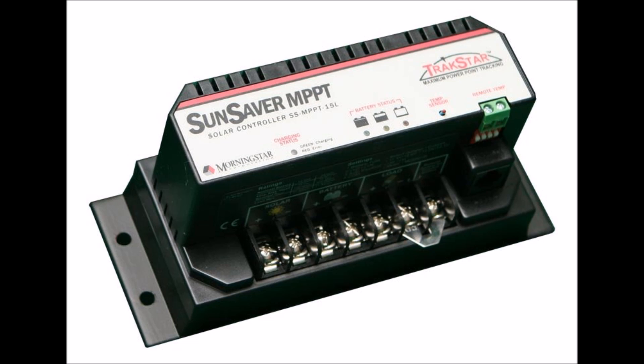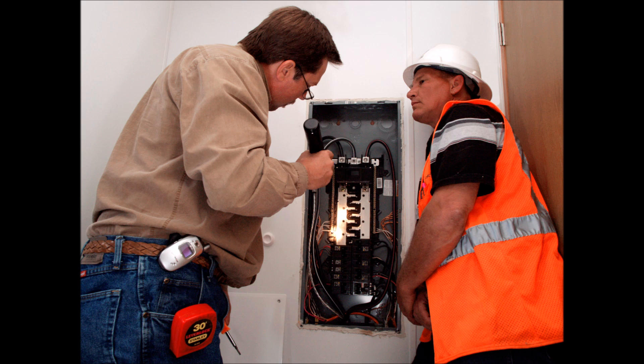That was also the case when maximum power point tracking charge controllers came along for off-grid systems. As long as they stayed under 600 volts to keep in compliance with electrical code requirements, they could do whatever they want. So eventually the industry settled on 60 cells. I'm not 100% sure why, but it seems to be because they can put 13 panels in series and stay under that 600 volt requirement.